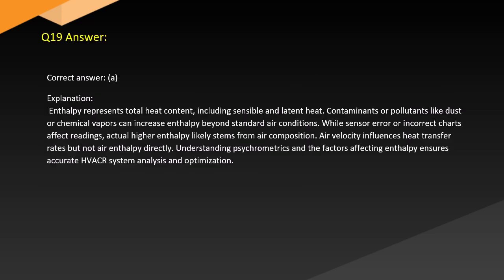Answer. Correct answer: A. Explanation. Enthalpy represents total heat content, including sensible and latent heat. Contaminants or pollutants like dust or chemical vapors can increase enthalpy beyond standard air conditions. While sensor error or incorrect charts affect readings, actual higher enthalpy likely stems from air composition. Air velocity influences heat transfer rates but not air enthalpy directly. Understanding psychrometrics and the factors affecting enthalpy ensures accurate HVACR system analysis and optimization.